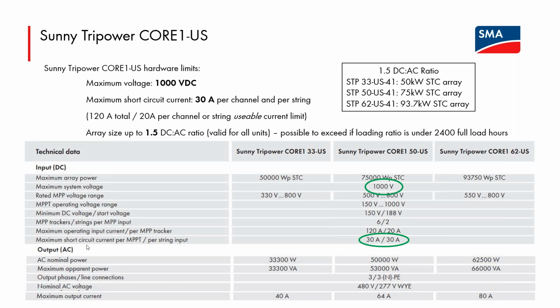There is also a short circuit current limit that SMA cares about. You'll notice that it says per maximum power point tracking channel / per string input, and the numbers on the data sheet are the same. You can drive each of the 6 tracking channels fully through a single positive and negative input for that channel, meaning you could use a Y branch connector to combine 2 strings out at the array and bring back a single positive and negative for that tracking channel and drive the inverter's tracking channel fully through that single positive and negative. So the short circuit current limit is the same per string input as for each of the 6 tracking channels, and that's 30 amps ISC.